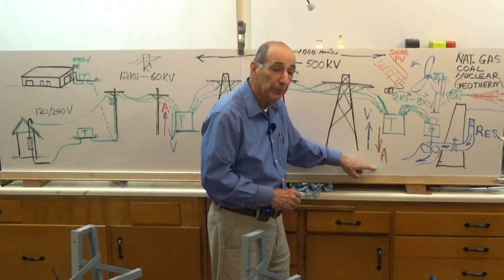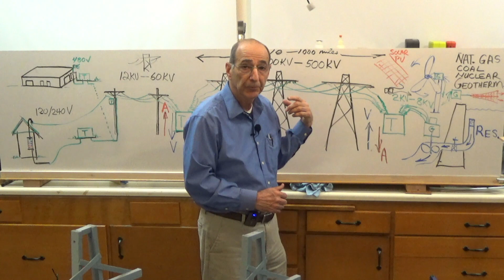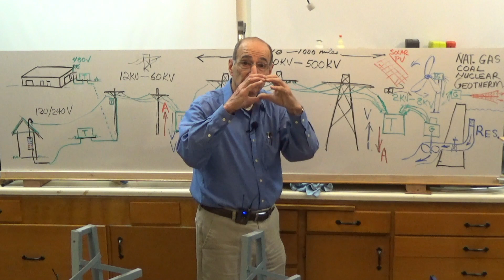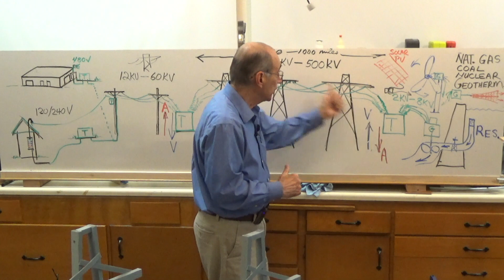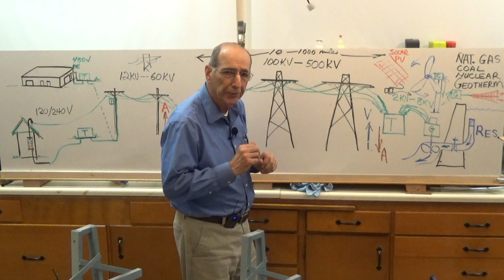What that means is, given a certain situation and a certain size wire, if I increase the voltage by a factor of 10 and reduce the amperage by a factor of 10, I can go either 100 times farther than with the lower voltage, or I can use wire that's 1/100th as large in cross-section, or some combination. I could go 10 times farther with wire that's 1/10 as thick. So we're going to explore that with some experiments.